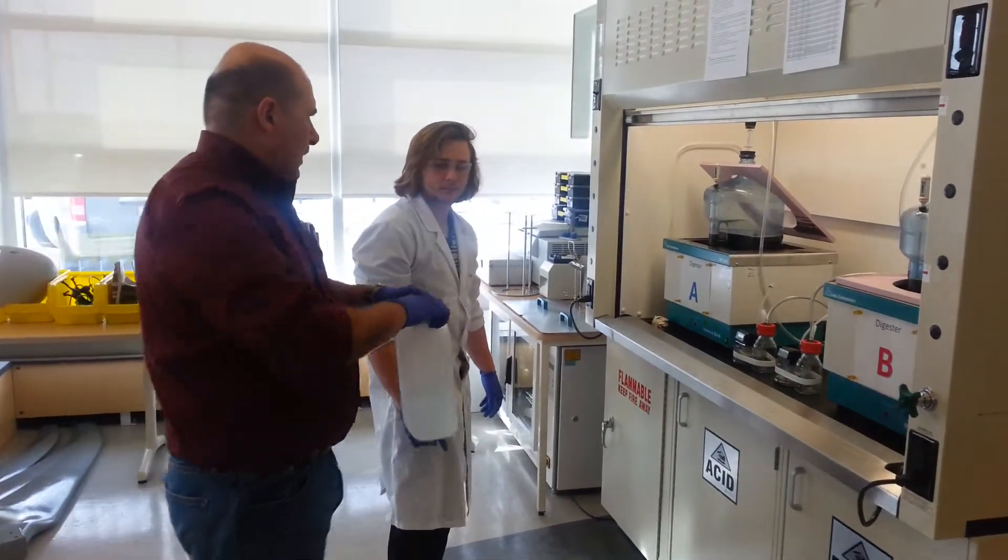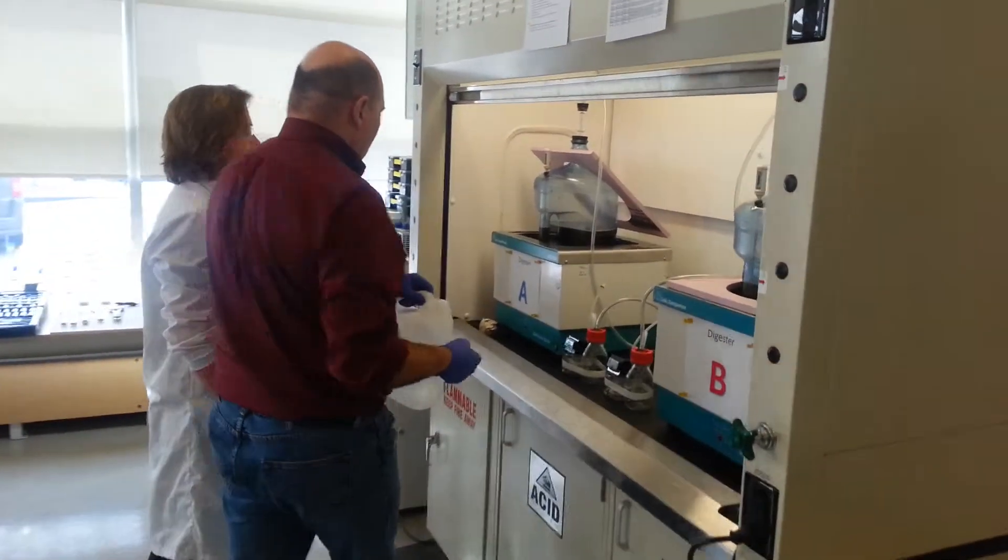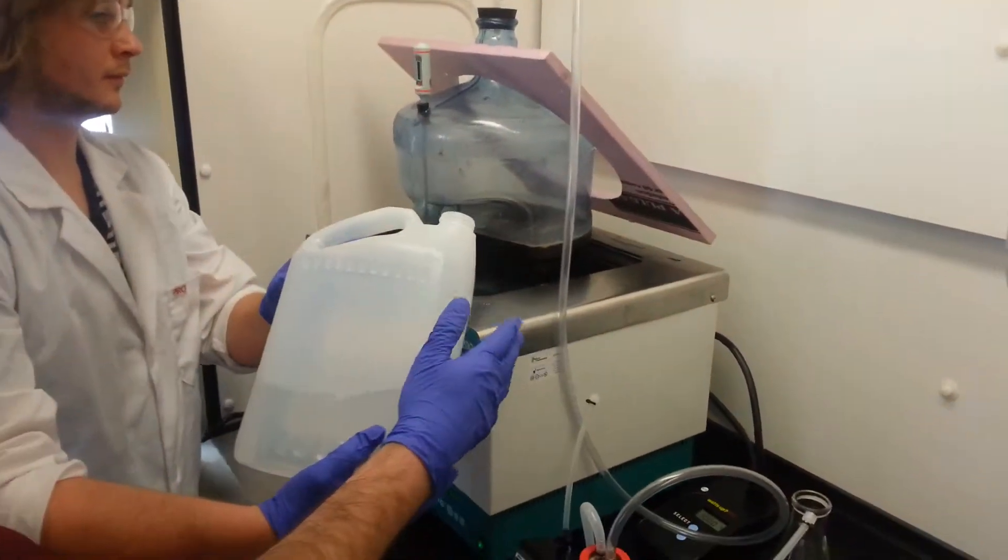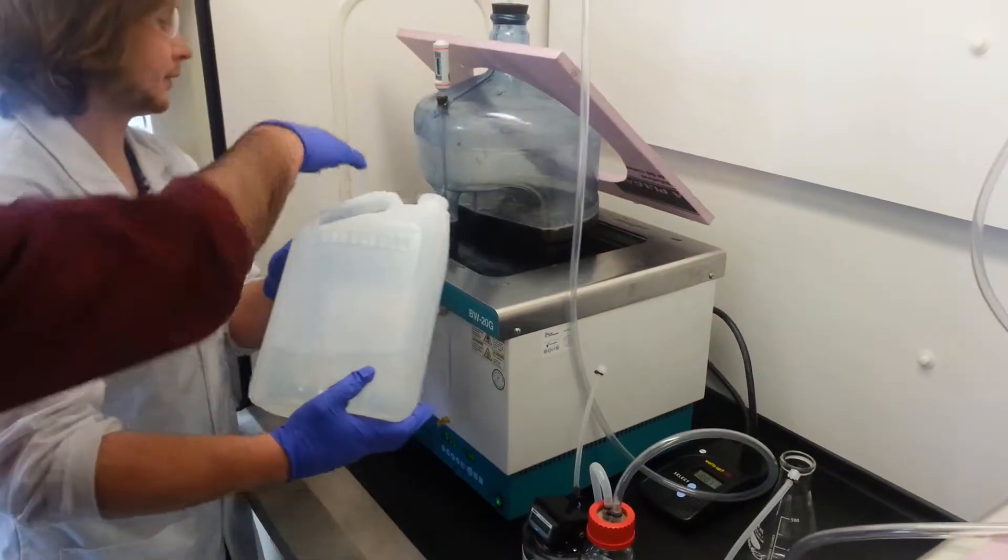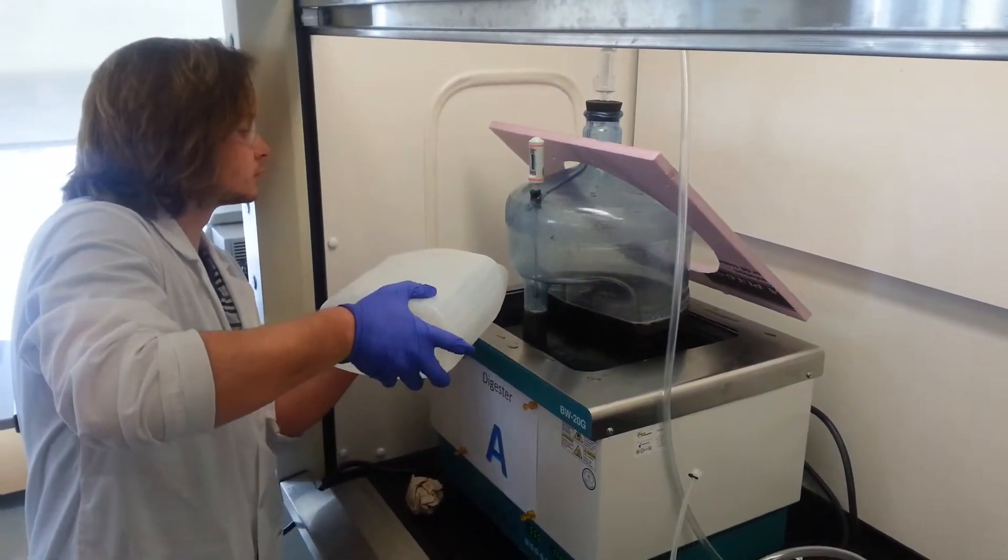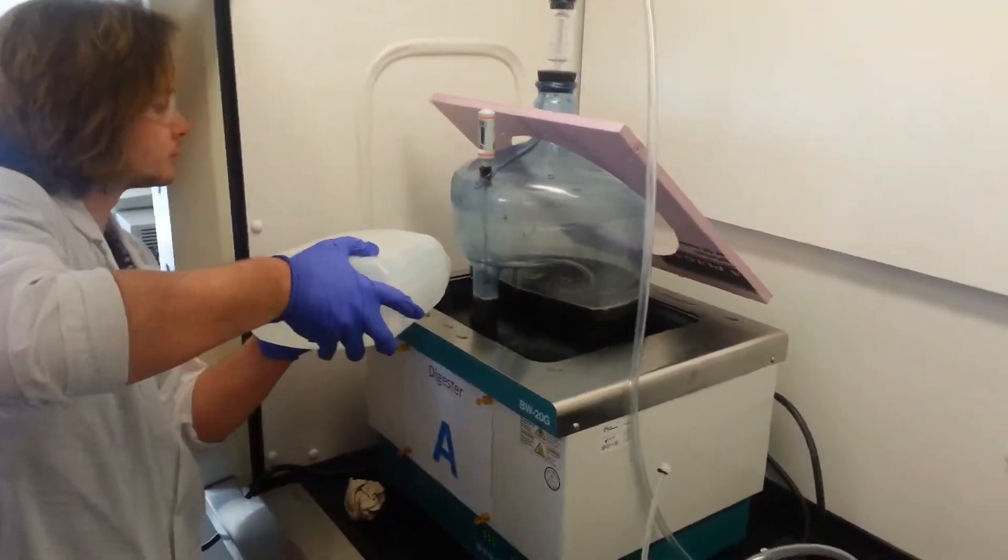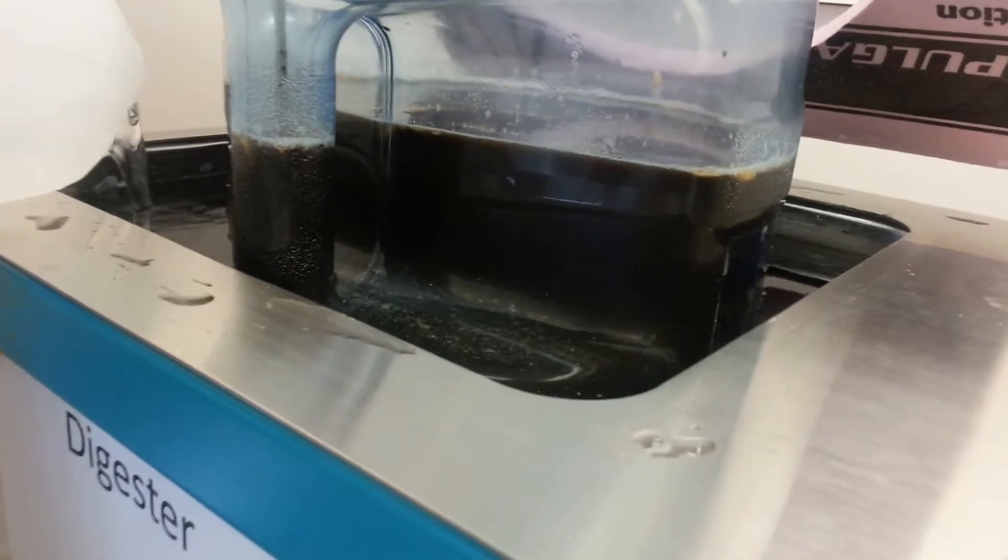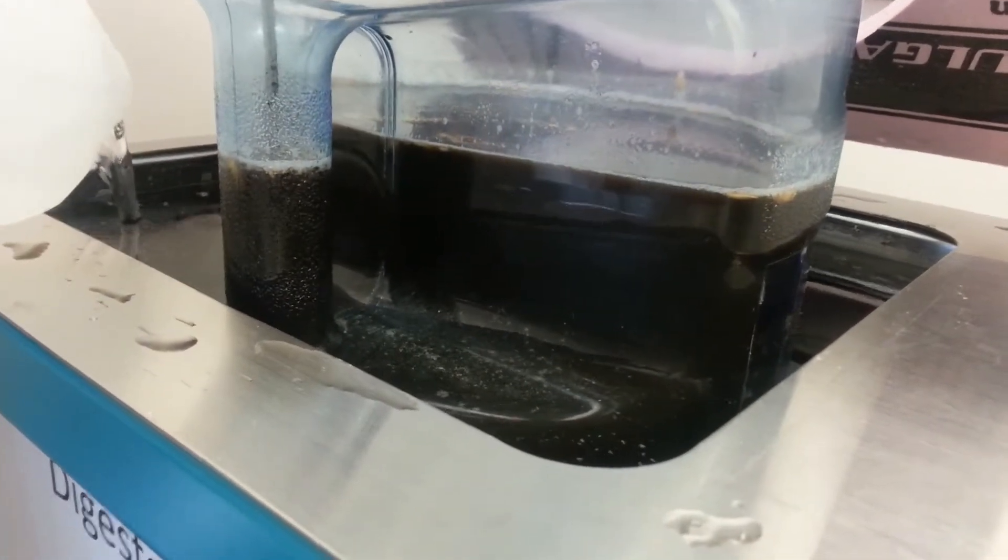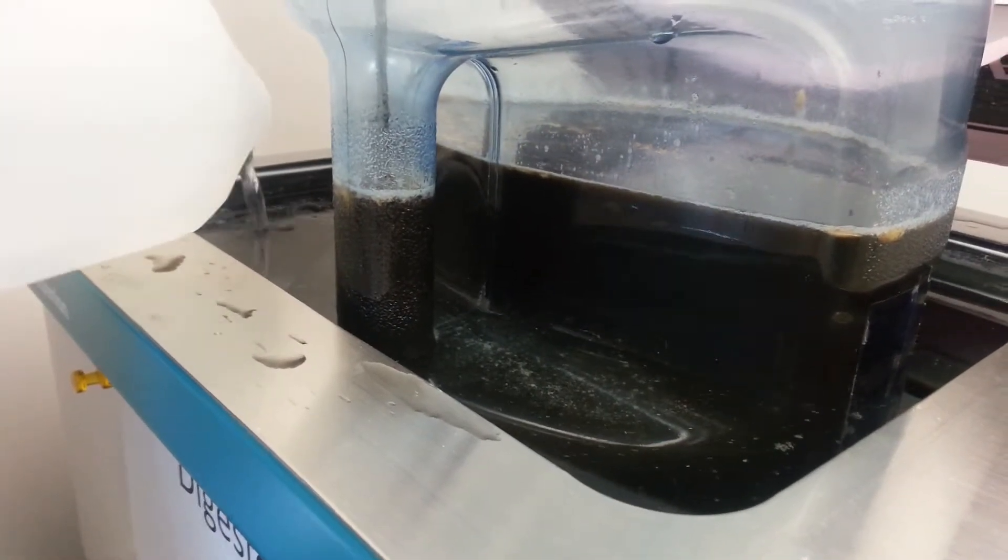You'll grab this 4-liter jug, fill it with hot water from the sink. Go to the corner away from the meters and everything. This corner here, or the opposite corner, and then slowly bring it up until you're roughly a centimeter from the top.